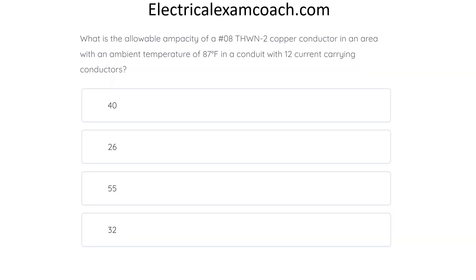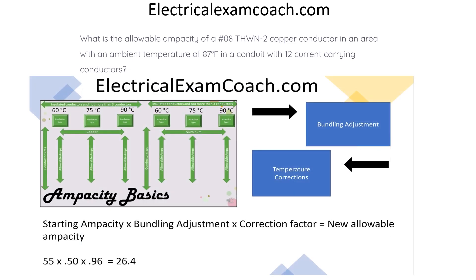What is the allowable ampacity of a number-8 THWN-2 copper conductor in an area with an ambient temperature of 87 degrees Fahrenheit and a conduit with 12 current-carrying conductors? The correct answer is 26 amps. First, we start at our primary ampacity table on the copper side and check if our insulation type is listed in the 90 degrees C column — it is. So we choose our starting ampacity of 55 amps. Then we head to our bundling adjustment table and find the adjustment factor for 12 current-carrying conductors.